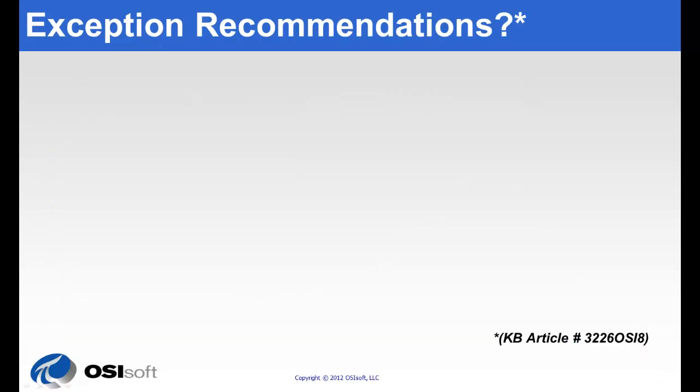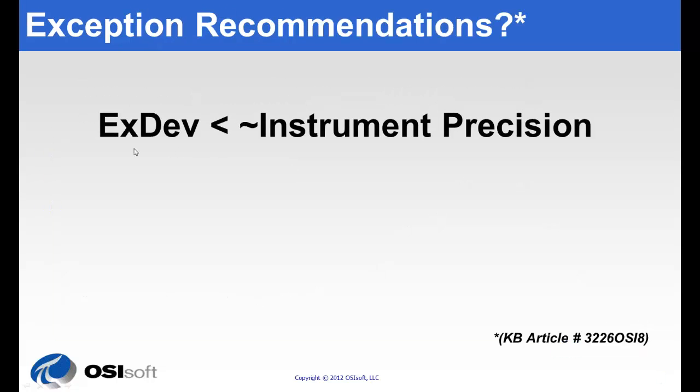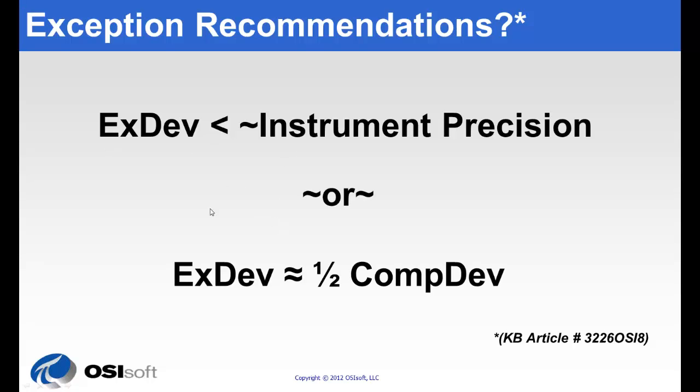OSISoft's recommendations for exception are that you set the exception deviation to a little bit less than the instrument precision or perhaps about half of the compression deviation. For more details you can consult this KB article 3226OSI8 at techsupport.osisoft.com.